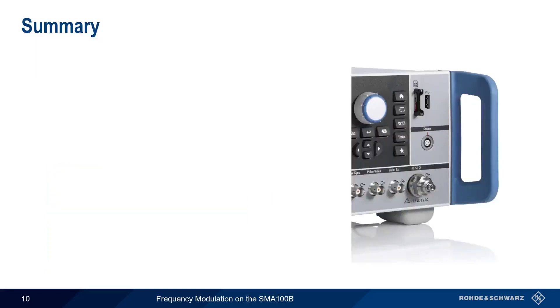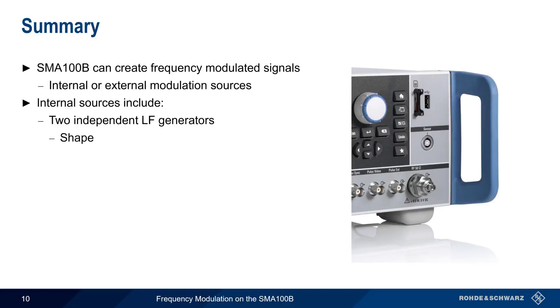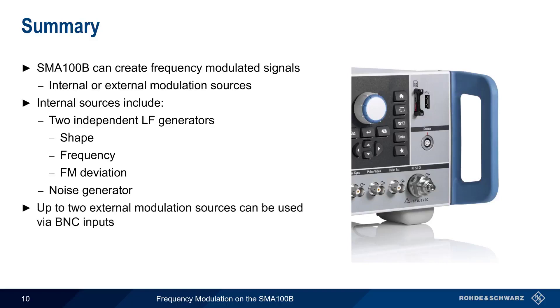Let's end with a brief summary. The Rohde & Schwarz SMA-100B analog signal generator can be used to create frequency modulated signals using either internal or external modulation sources. The available internal sources include two independent LF or low-frequency generators, which can provide a variety of different shapes such as sine, pulse, and others. We can also specify the frequency of the modulating signal and the FM deviation. In addition, the SMA also has a configurable internal noise generator that can be used as a modulation source. And finally, external modulation sources can be connected to either or both of the SMA's two external BNC connectors.